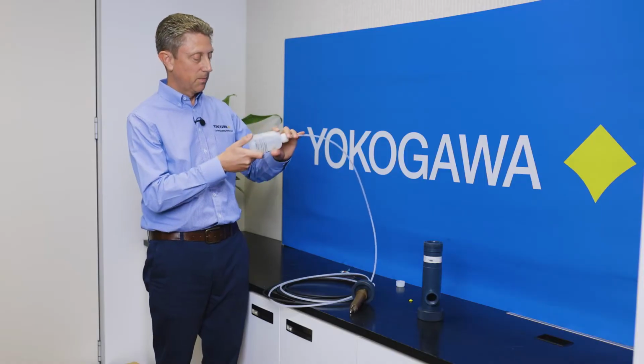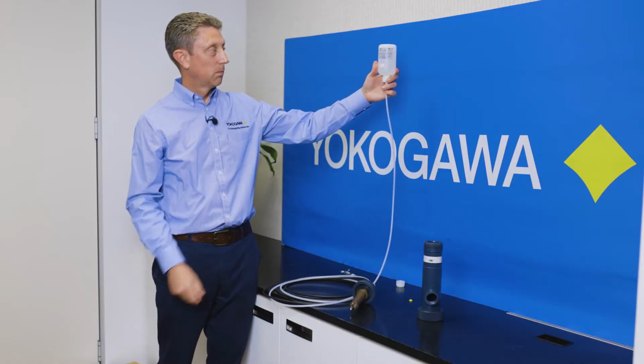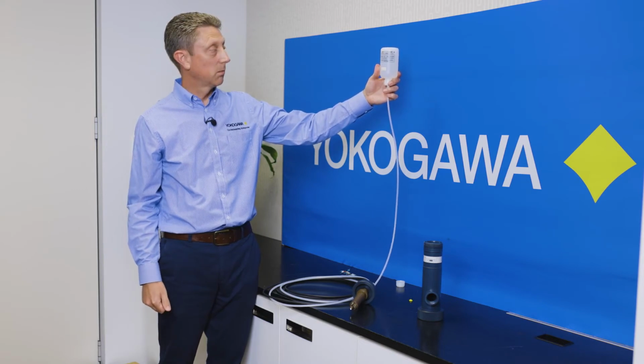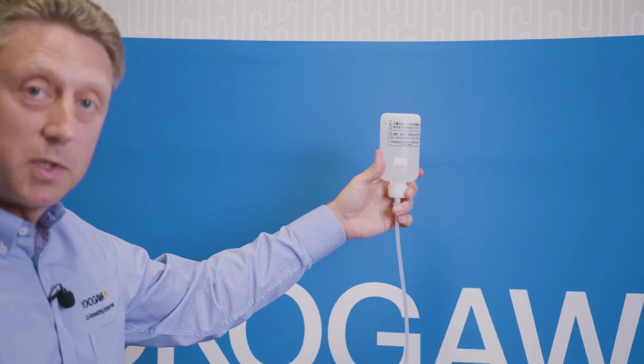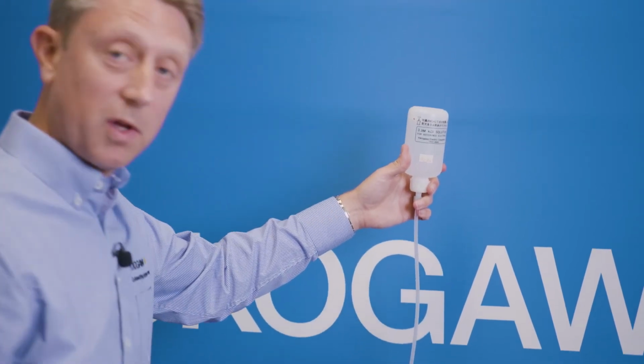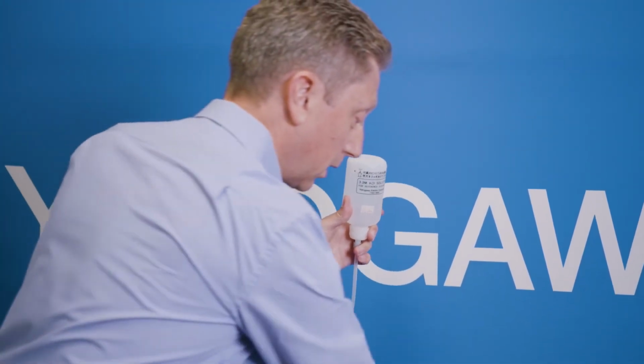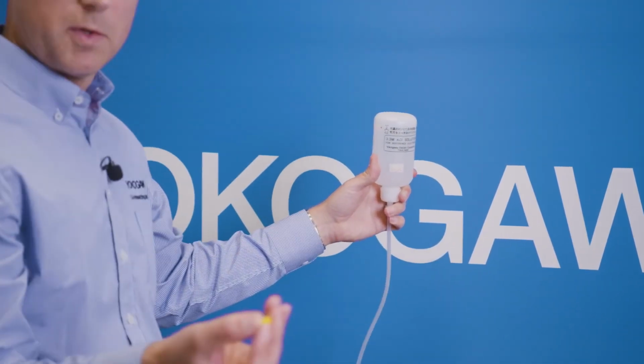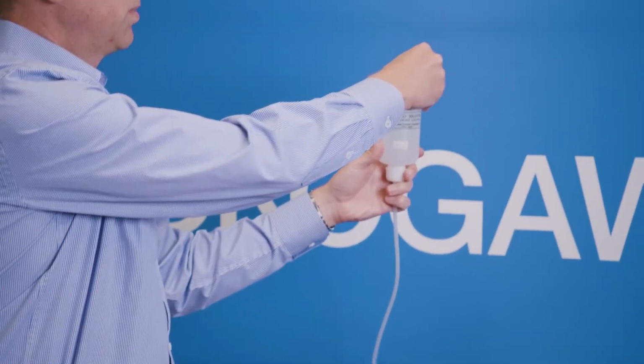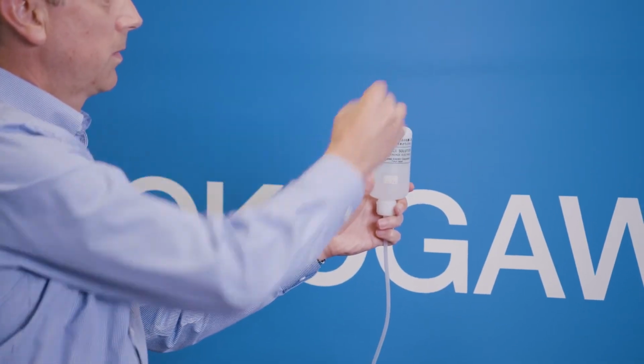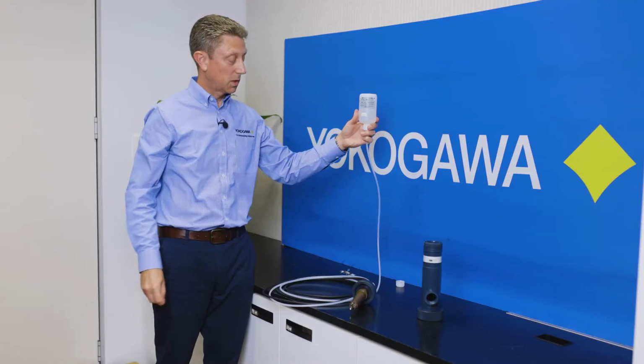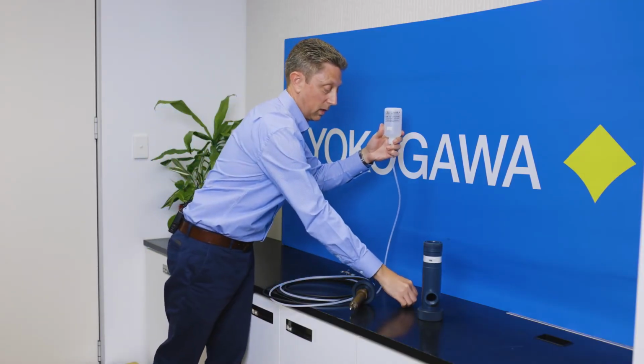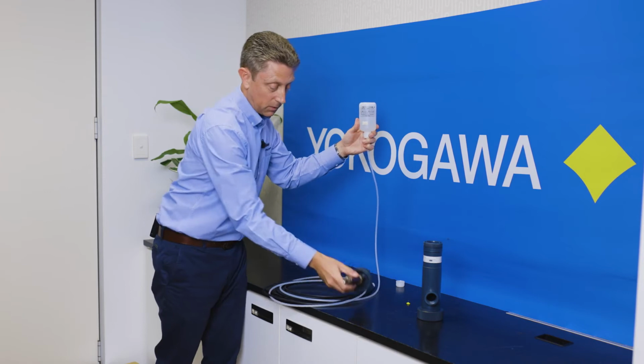and it's at this point that we'll clamp our reference solution into its holder at a position that's elevated above the height of the sensor. We take our thumbtack and we can use it to pierce 3 little holes in the bottle here, which, as I say, will allow air to flow in and the reference solution to flow out.